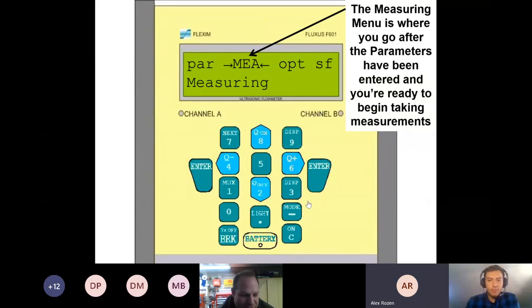Also, one thing to jump in on that Zach mentioned about the sound speed diagnostic while we brought it up: that sound speed of 2000 is also the sound of empty pipe. So sometimes you might think a pipe is full, but it's not. We ran into that at a wastewater facility in New Haven, Connecticut, where we were trying to measure, and when we set up the system, there's nothing flowing. But the minute they turned on their pump, it siphoned the pipe empty. So we went from fantastic diagnostics to that 2000 sound speed diagnostic, which led us to look into it. And that's when the engineers got involved and realized that they have a siphoning effect and that you can't measure in the spot that they originally wanted to.